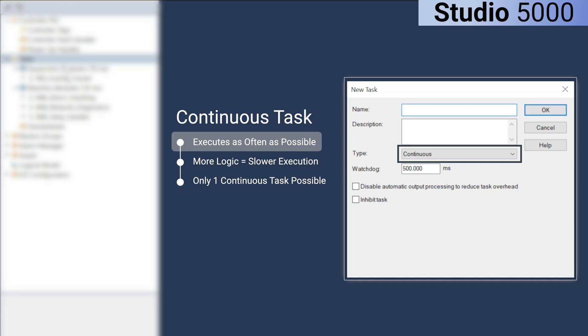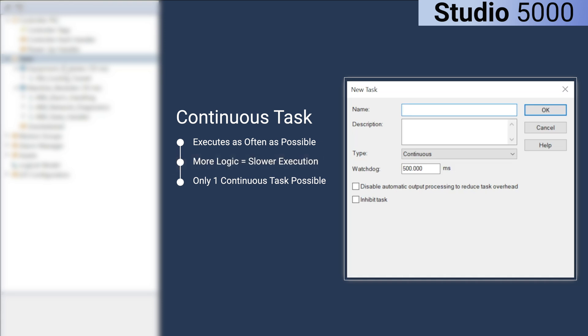A continuous task executes as often as possible, which is the default mode of execution. It runs continuously and its scan cycle depends on how much logic is present in the task. The more logic a continuous task needs to process, the slower its execution will be. Only one continuous task can exist in a Rockwell PLC program.